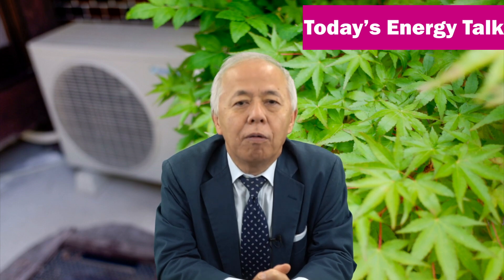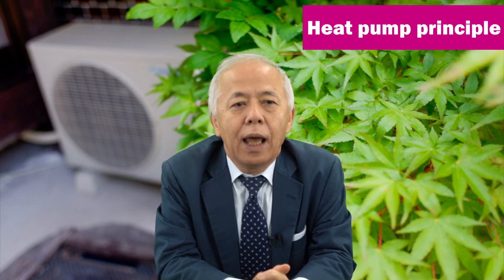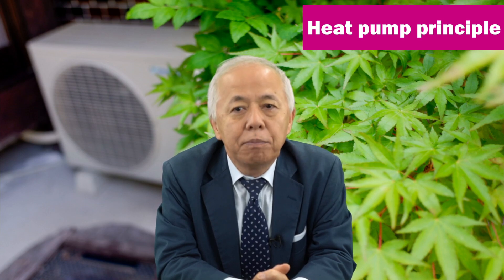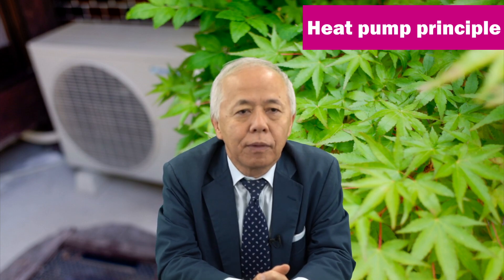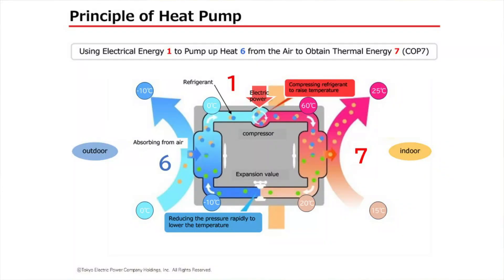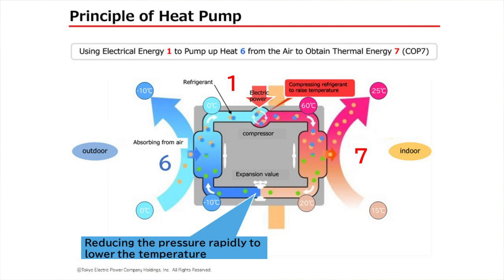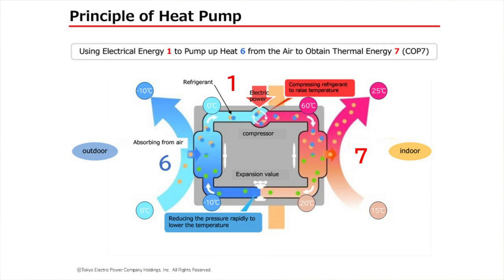Let me explain the principle of heat pumps. A heat pump works by pumping heat from the atmosphere and transferring it through heat exchange. Please take a look at this illustration. Heat exists in the air. The heat is captured in refrigerant. By compressing it, it is made hotter and the heat is exchanged inside the room to warm the room. The temperature of the refrigerant is lowered by releasing the heat, and the temperature is further lowered when the refrigerant is depressurized by an expansion valve. This cold refrigerant again absorbs heat from the atmosphere.